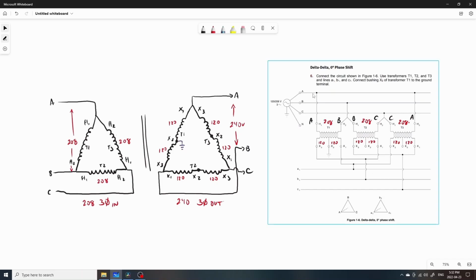We have H1 to A, which is seen right here. H1 is going to A, then H2 is going to B. H1 of T2 is going to B, and H2 of transformer 2 is going to C - that's tied to C. Finally, transformer 3's H1 is going to C, and H2 is going back to A. So we've got A to B, B to C, and C back to A.